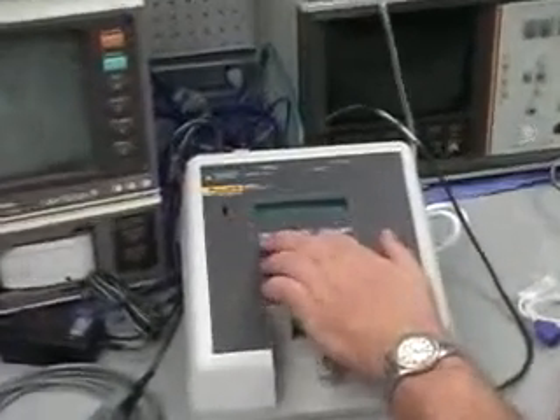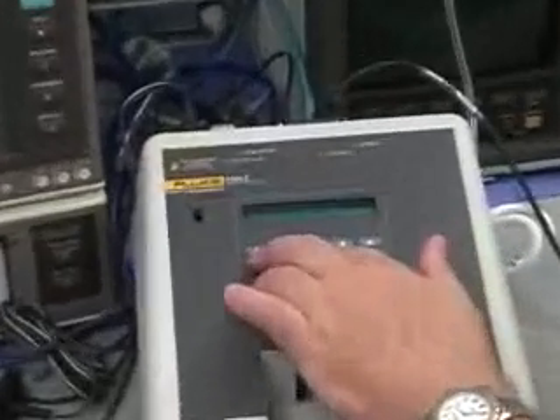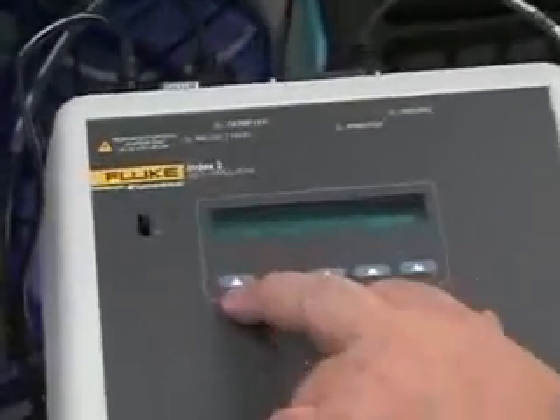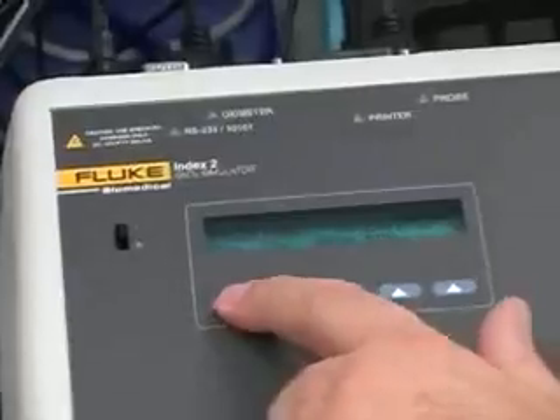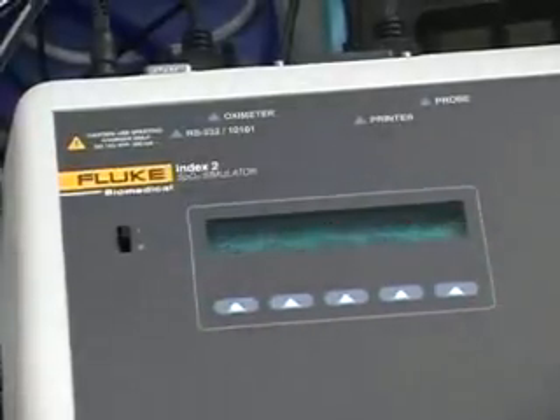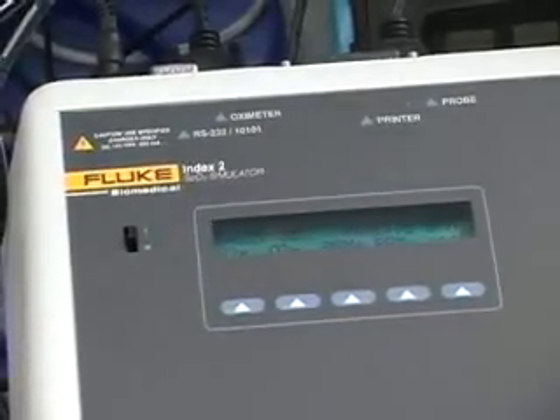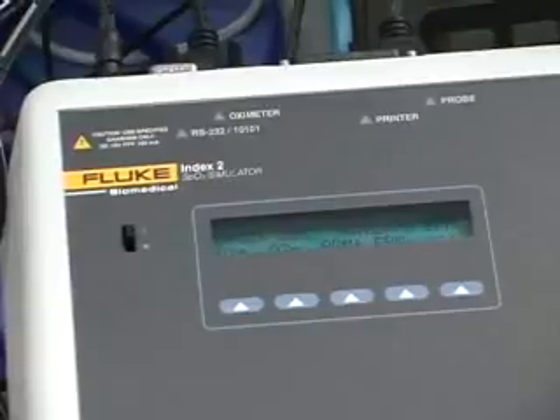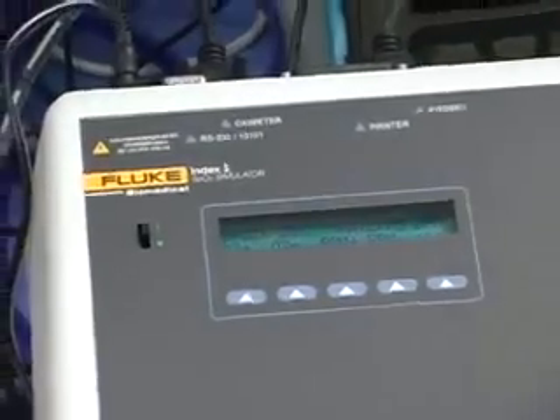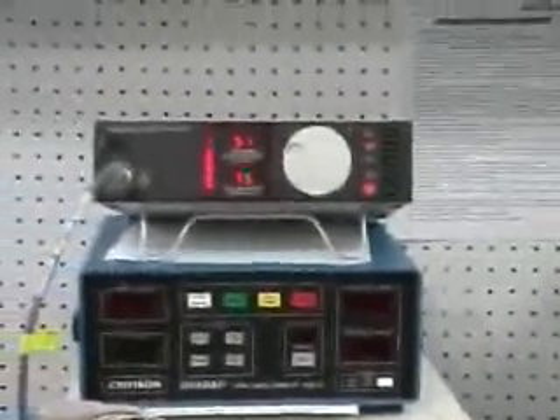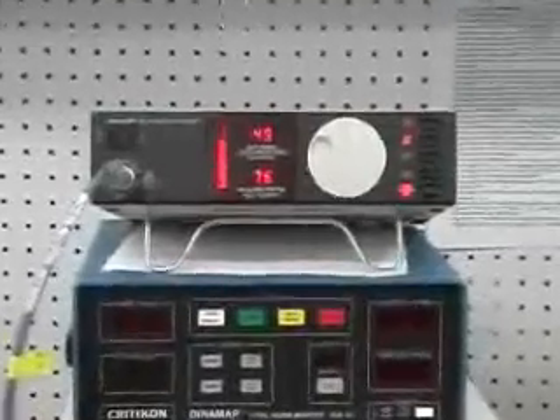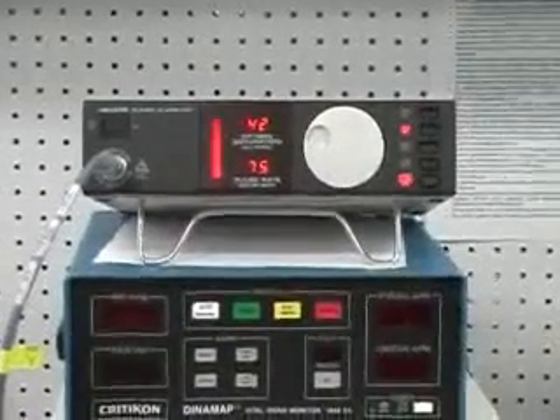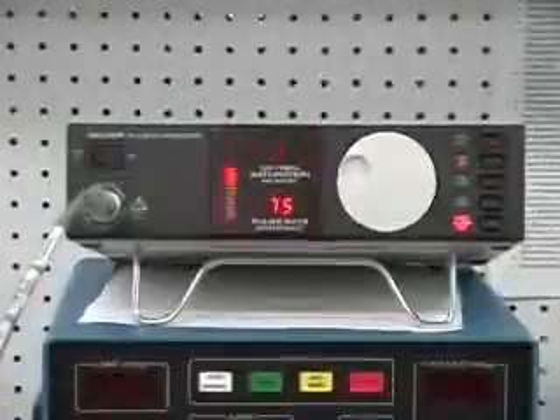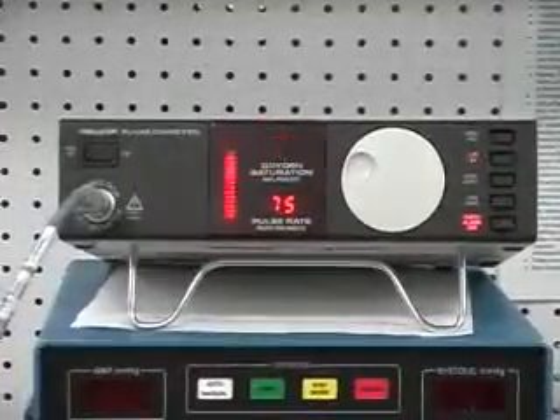The display and simulation will wrap around, so if I increase it again from 100, that will wrap it back around to 35% as the very bottom. And with this one, you're looking typically at about a 2% accuracy from 70 to 100. Usually under 70%, many of these devices, the monitors themselves, aren't really specified.